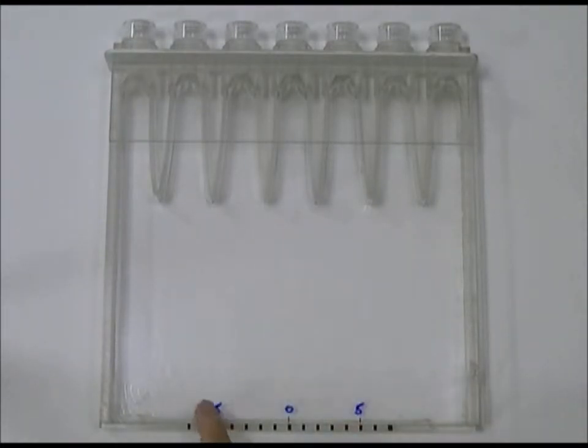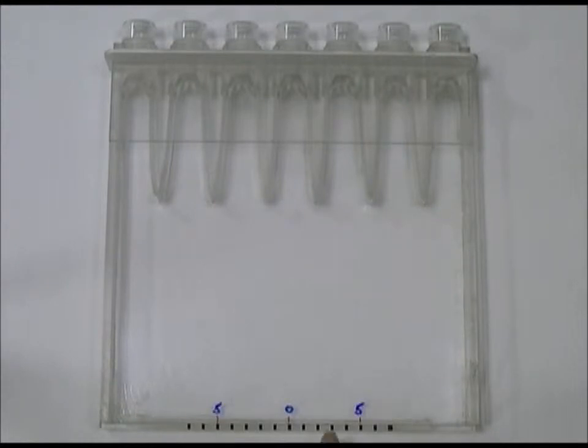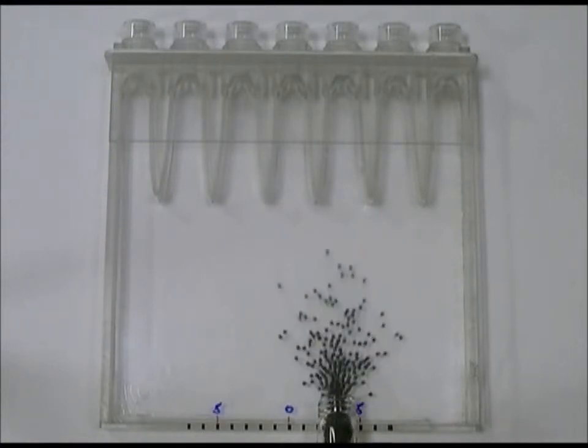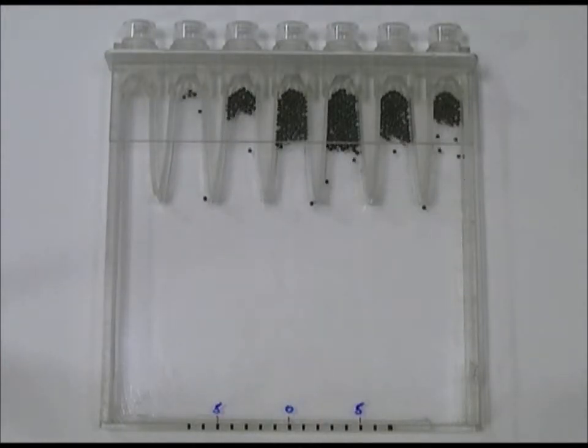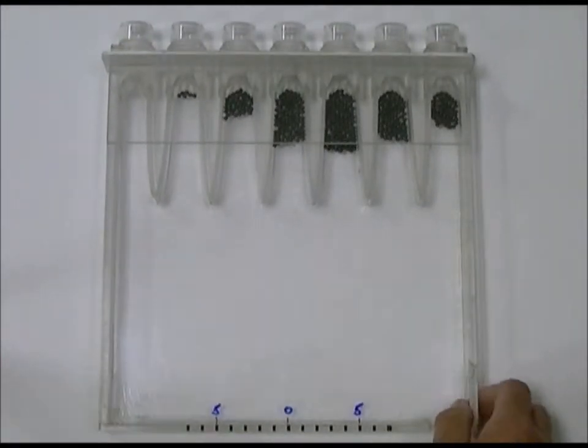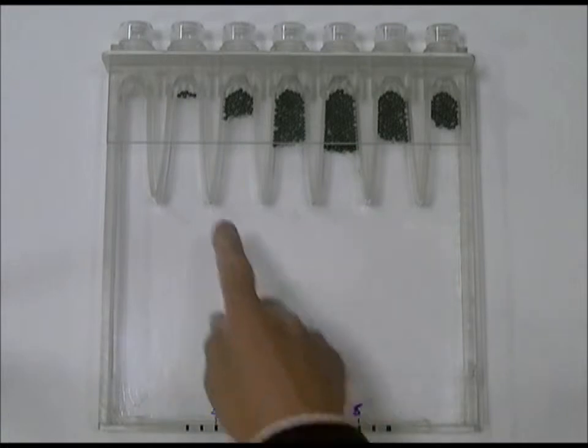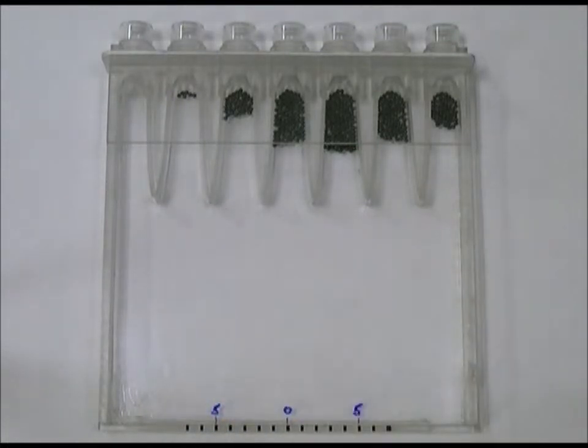I've got a scale that goes from 5 on the left to 5 on the right with 0 in the middle, and I'm going to choose a position of 3 on the right as the position where my gamma-ray will interact with the crystal. So I have my lead shot representing the light photons spreading out and being collected by all the photomultiplier tubes. You can see that we get a distribution with most light collected by the tube opposite where the gamma-ray interacted, and less on either side.